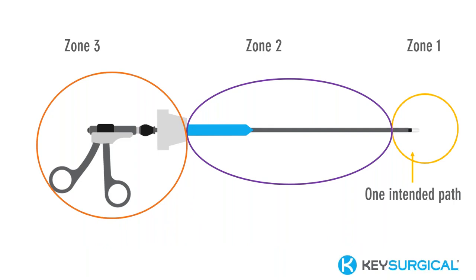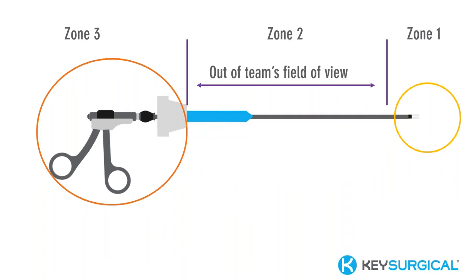Another way to consider instruments is to revisit the instrument itself, and note that a large portion of the instrument that's insulated is not visible when the current is being applied through that instrument. For the purpose of this discussion, we split the instrument into 3 zones. Zone 3 is the handle and the top of the trocar. Then Zone 2, and then Zone 1. Zone 1 is the intended path, right where we want the current to be applied. For a majority of the case, Zone 2, which is all insulated, is out of the surgical team's field of view. Often insulation damage is not visible to the naked eye without magnification or insulation testing, and those serious complications also might not be visible, as we saw in the last video.